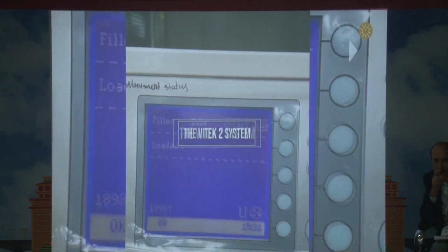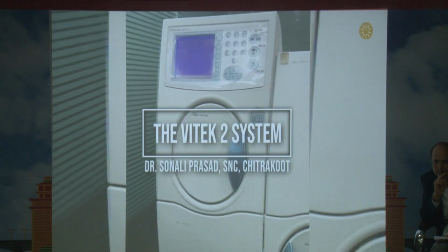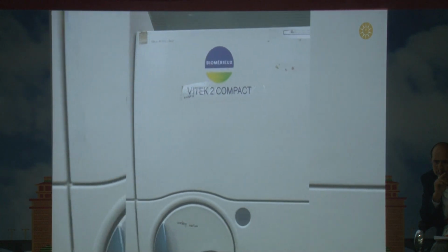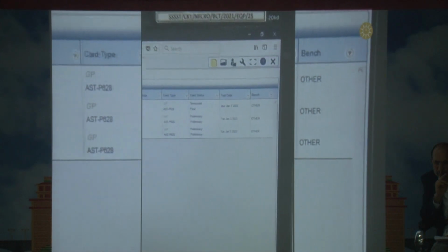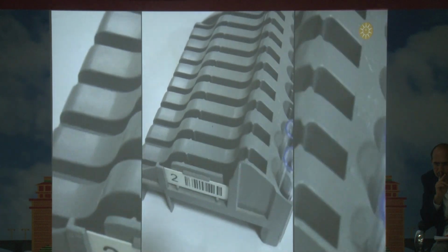Good evening, judges. The Vitek 2 device is an automated photometric system which is used for the identification and antimicrobial susceptibility testing. This instrument reads the kinetics of the growth every 15 minutes using an optical system which combines photometer and multi-channel fluorimeter readings to assess the fluorescence, turbidity, and the colorimetric signals.